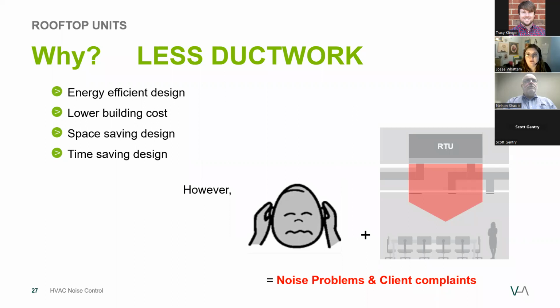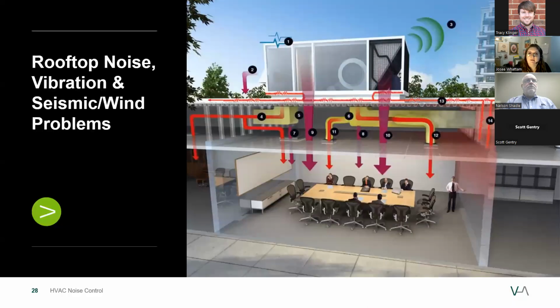However, high sound power levels plus an RTU located directly over an occupied space could result in a noise problem and client complaint. In fact, the only reason that an RTU would not be placed directly over an occupied space is out of concern of a noise problem. So unfortunately, we have two problems colliding here. One, the RTU has high sound power levels, and two, the majority of RTUs are placed over a sound sensitive space. So let's talk now about those 14 noise pathways of an RTU that can invade an occupied space.